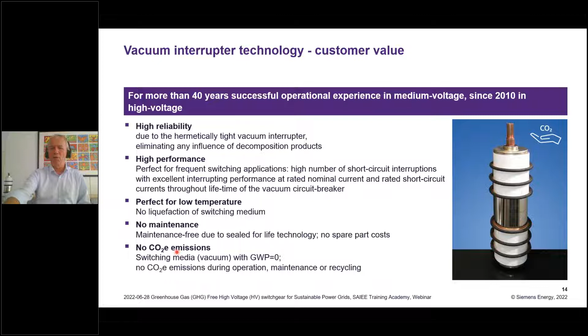So it's a higher number of short circuit interruptions possible. It has an excellent rated nominal current and rated short circuit currents over the lifetime. It's perfect for lower temperatures down to -60 degrees Celsius. It doesn't have any maintenance connected, so you can switch up to 10,000 times. And once you achieve that, which is very seldom, you exchange it completely. So no maintenance needed, and there are no CO2 emissions connected to that vacuum interrupter.